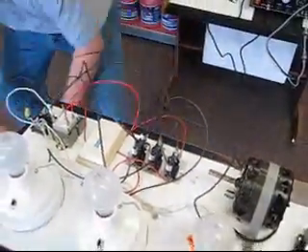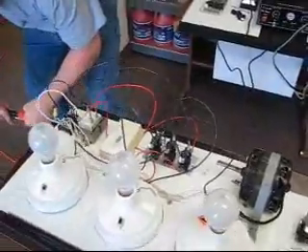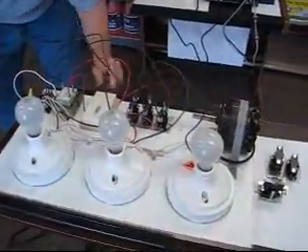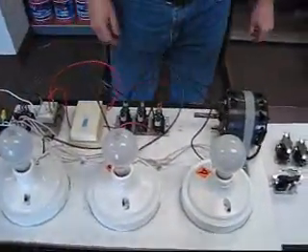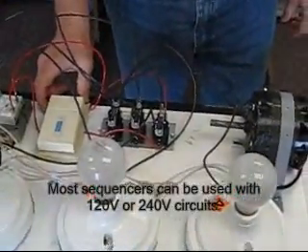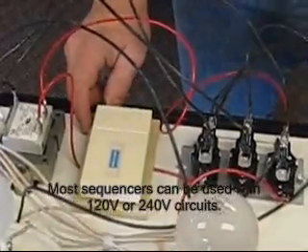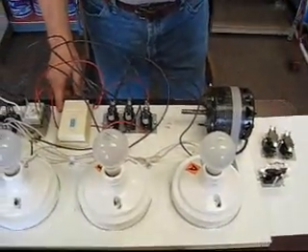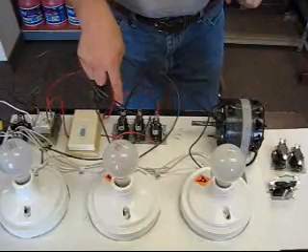Our sequencer is all hooked up for testing. I'm going to plug it in. We've got power coming to it. Let's turn on our thermostat. Now there's always going to be a slight delay before the first switch kicks in.